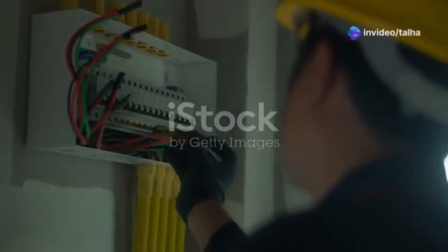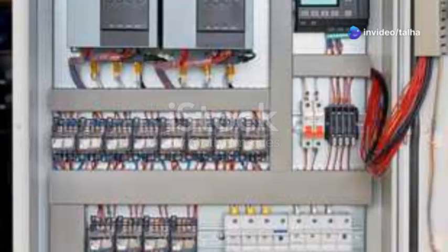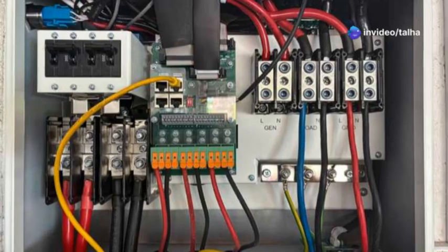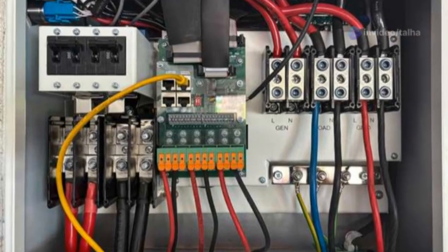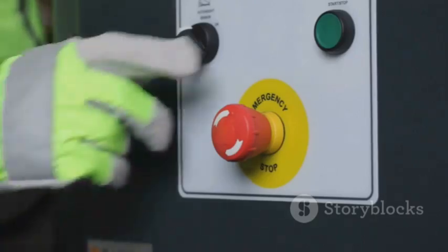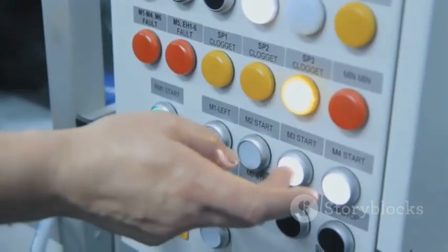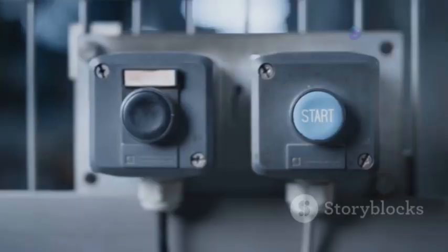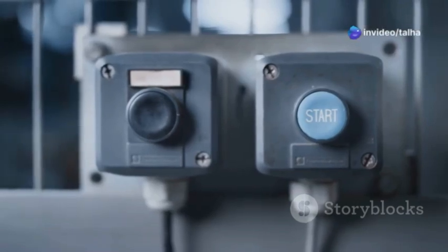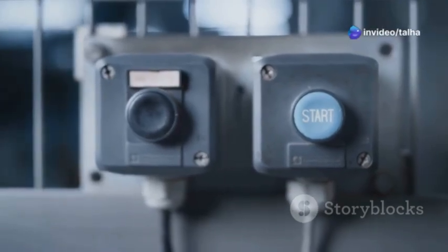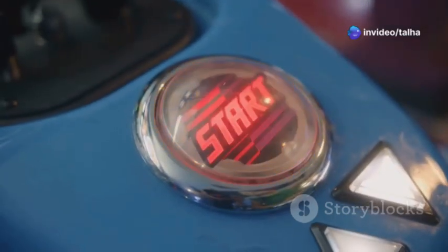Section 4. Wiring the control circuit, controlling the power. Now for the brains, the control circuit. This tells the contactor when to turn on and off. First, connect the stop button in line with the control circuit. This makes sure hitting stop cuts the power instantly. Next, connect the start button alongside, but with a normally open contact of the contactor in line. This makes it stay on.